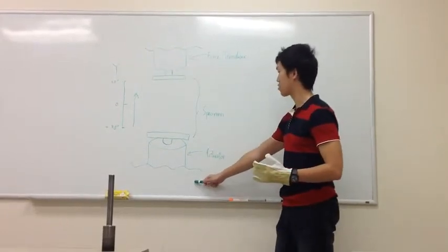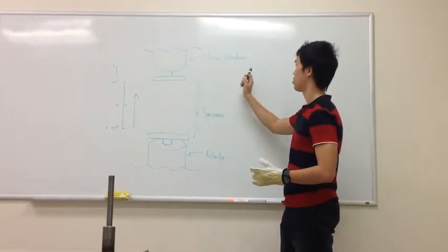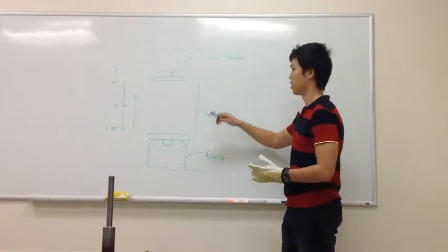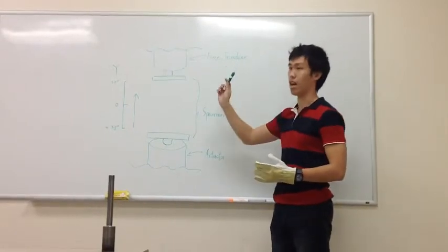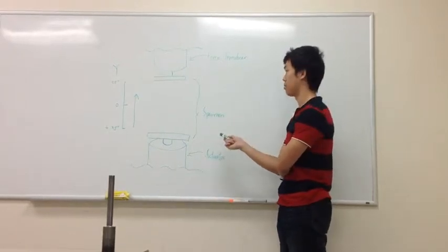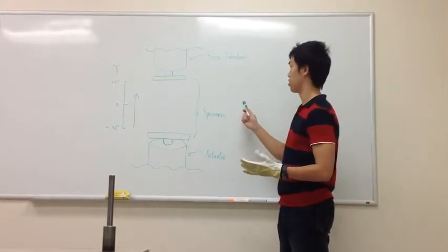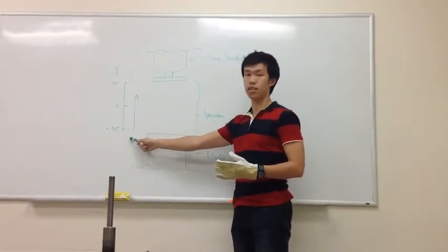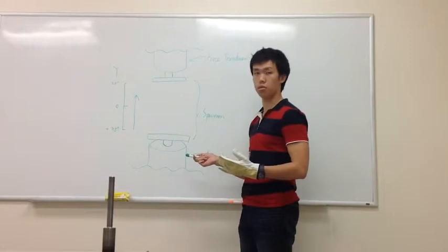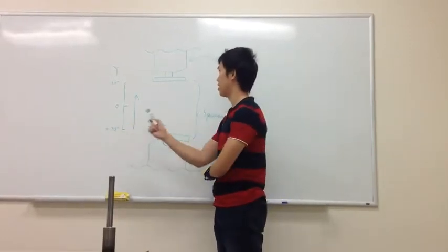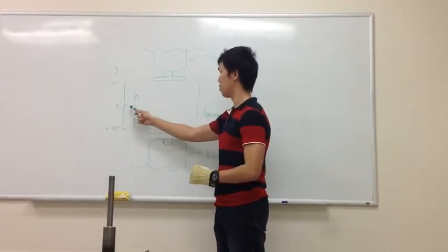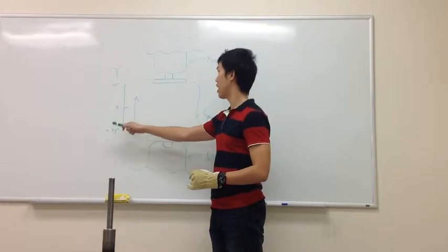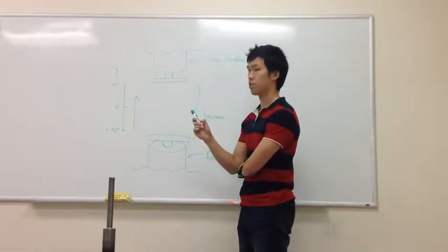The bottom is the actuator. The top is the force transducer, which is attached to the crosshead. And you will install your specimen in between. You can adjust the height of your crosshead, which is also the force transducer, according to the size of the specimen. So after you've done your adjustment, you install the specimen. And this is the sign convention that MTS use, which will make sense in a minute. So think this as an inverse y-axis. Zero will be in the middle, positive 1 is on the bottom, and the negative 1 is on the top.